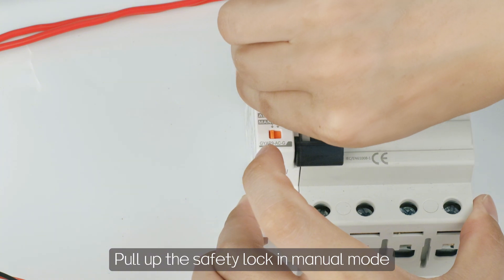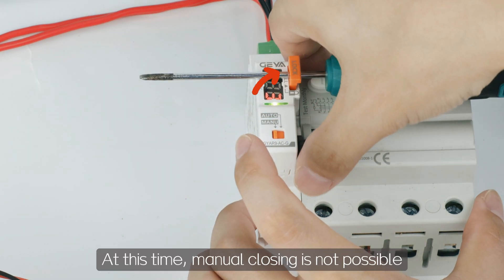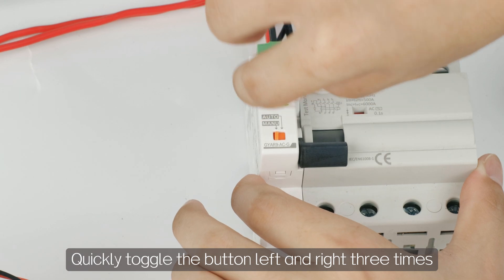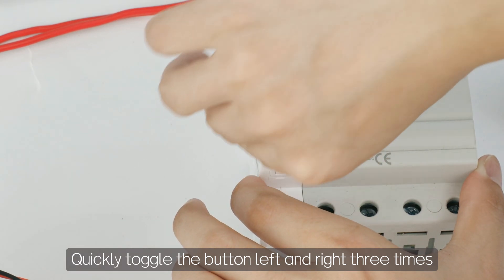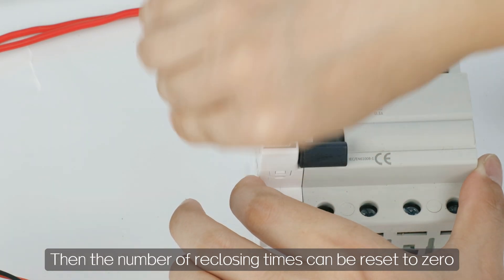Pull up the safety lock in manual mode. At this time, manual closing is not possible. Quickly toggle the button left and right three times. Then the number of reclosing times can be reset to zero.